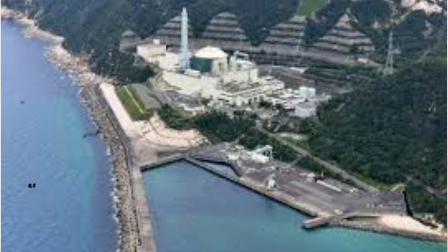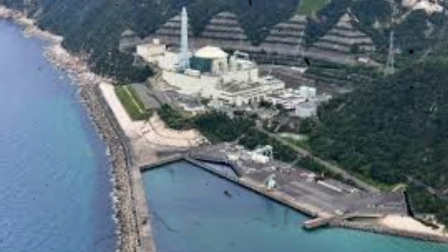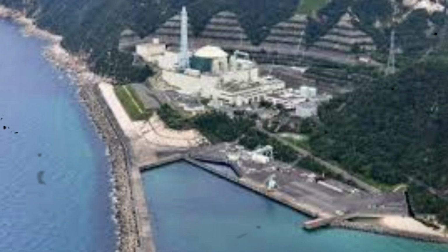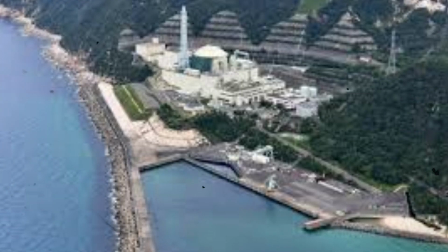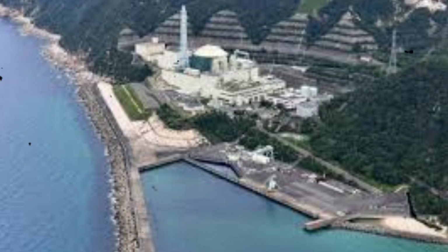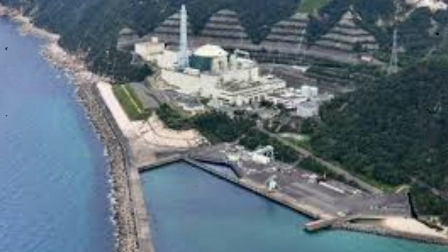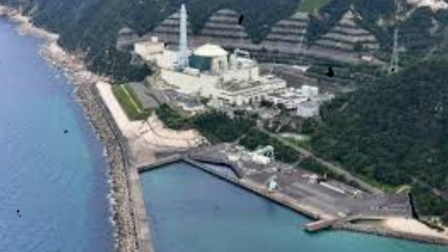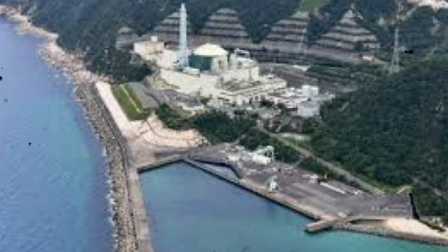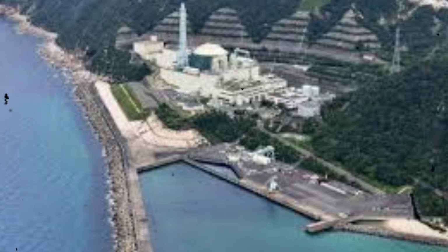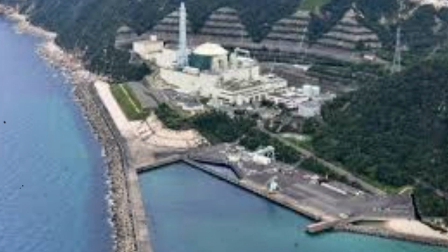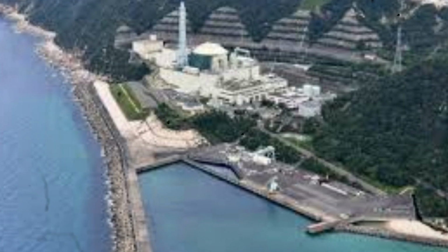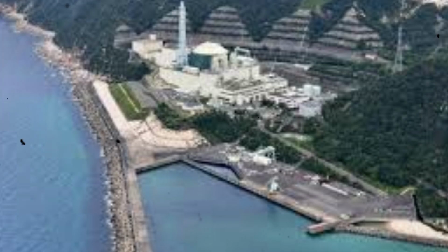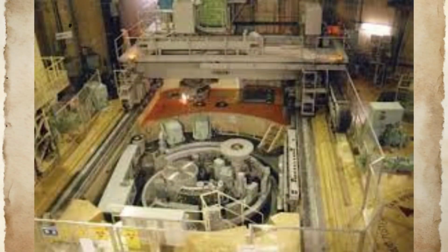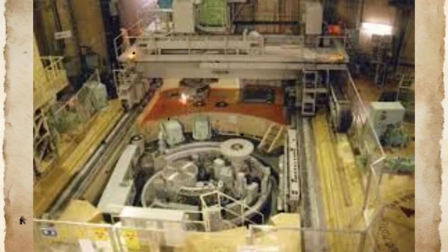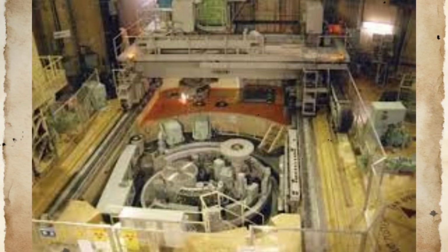The timing of the final failure during 40% power operation initially appeared inconsistent with a fatigue mechanism that should worsen with increased vibrational loading. However, detailed analysis revealed that the crack had propagated to near-critical dimensions during previous high-power operation. The final fracture occurred when remaining wall thickness could no longer support even the reduced loads present during partial power operation. This failure timing created additional diagnostic confusion for operators.